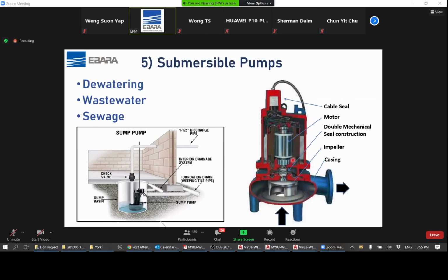A submersible pump that is used for wastewater is usually made of a very heavy duty material, usually cast iron. In some cases, for example in a corrosive environment, it can also be made out of stainless steel or other more resistant alloys. Even the impeller is made of cast iron for its hard wearing properties, because this impeller takes a lot of abuse from the bottom. When we say wastewater and drainage water, there's a lot of dirty content inside the water, so it has to handle a lot of this to pump out. This is a subject by itself which we will talk about in the next few slides.